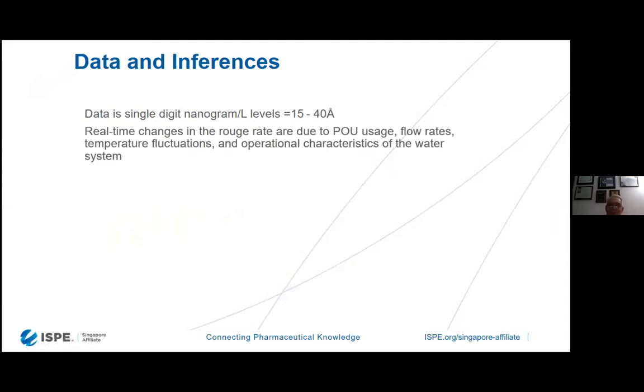So let's talk a little bit about our data and what we actually saw. Data is in single-digit nanogram levels, somewhere between 15 to 40 angstroms. That's where the data is coming through most of the time. You need a very accurate instrument in order to run down at that particular level. Real-time changes in the rouge rate, though, are due to the point of use usage, opening up valves, our flow rates within the system, temperature fluctuations, and the overall operational characteristics of the water system. When the operational characteristics of the water system change due to pressures, flows, temperatures, etc., you'll have changes in the rouge. So you can't say any one particular level is best for rouge or rouge development. You have to deal with the rouge as you operate your water system.